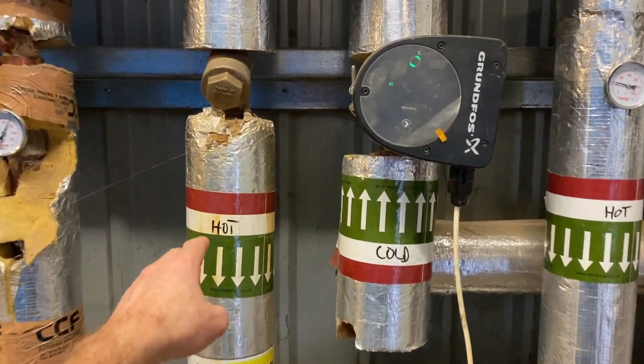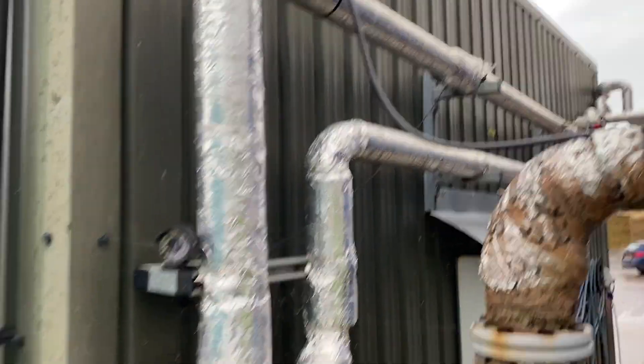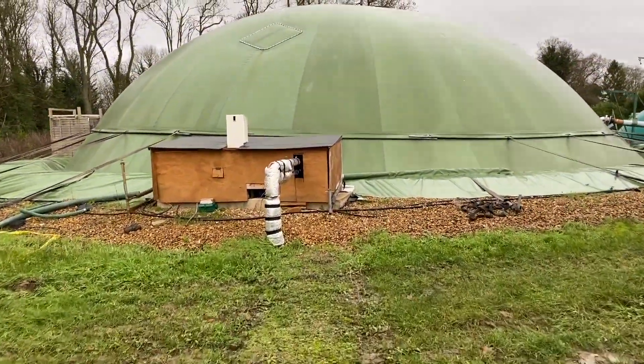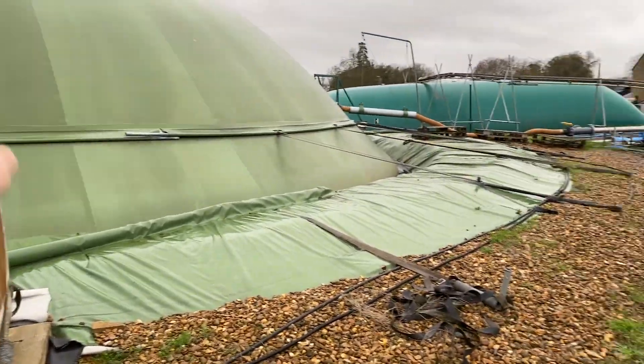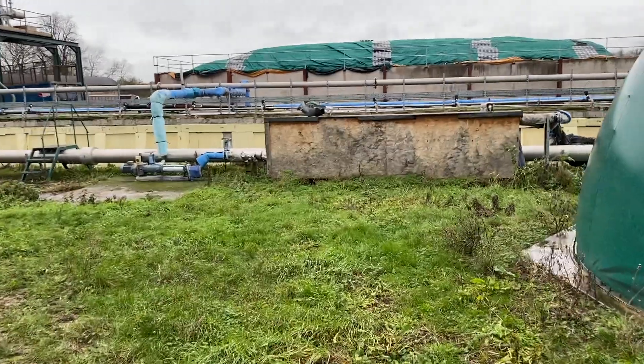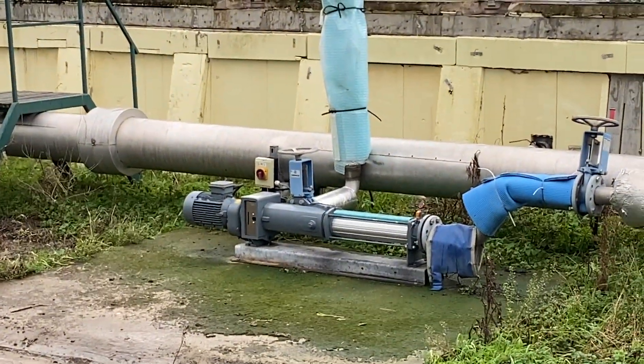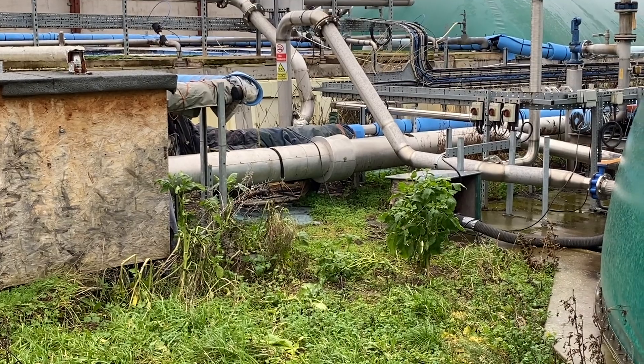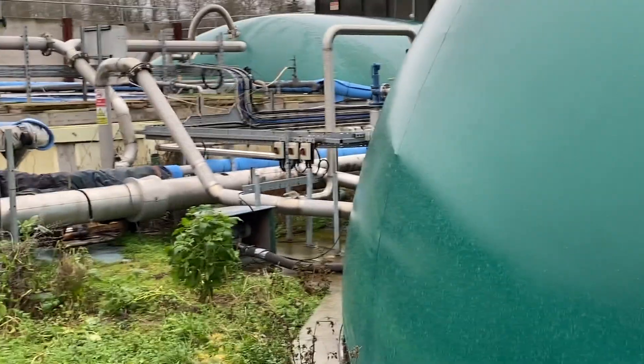And then this one here actually heats the tank and keeps that all warm and our secondary digestion — so that's outside. This pipe here runs from inside and then heats up the Combi bag. It goes underground, pokes up over here and heats up our secondary digester. There's a whole load of coils underneath this big bag and that takes the heat and keeps that one warm. Then we've got another pipe run that goes out inside this box — a series of pipes going back and forth with a water jacket over the top. The Netzsch pump runs all the time pulling digestate out of the tank and into that box there, the heat exchanger. That big silver pipe then goes back to the front of the tank and puts the hot liquid back in to keep the whole tank pretty hot — it needs to be about 38 to 39 degrees in there.